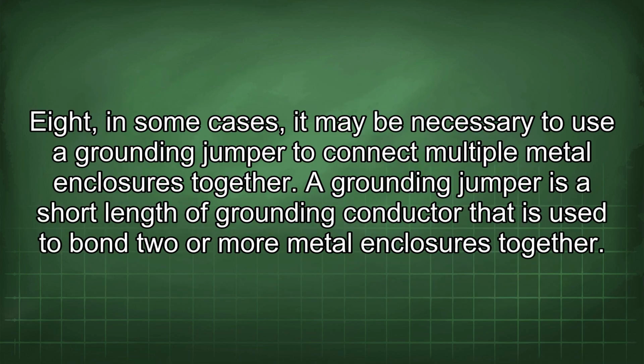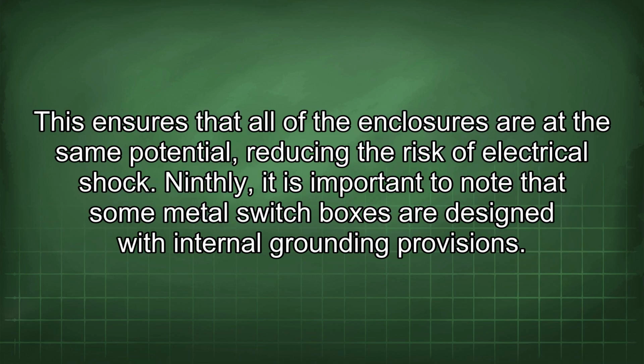8. In some cases, it may be necessary to use a grounding jumper to connect multiple metal enclosures together. A grounding jumper is a short length of grounding conductor that is used to bond two or more metal enclosures together. This ensures that all of the enclosures are at the same potential, reducing the risk of electrical shock.